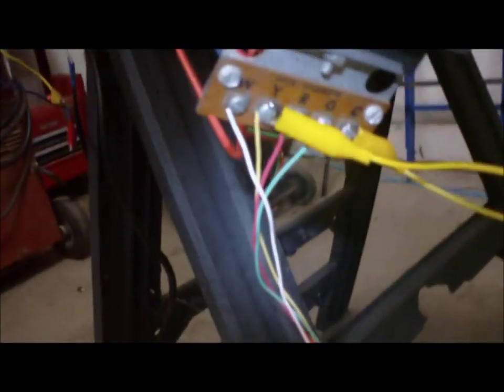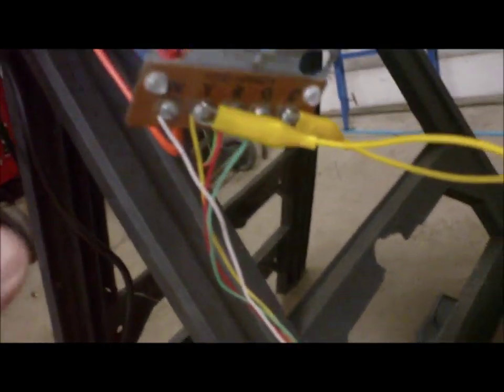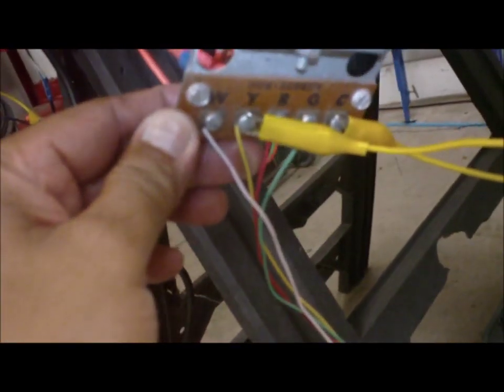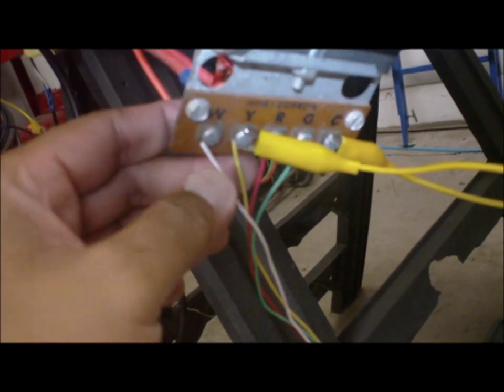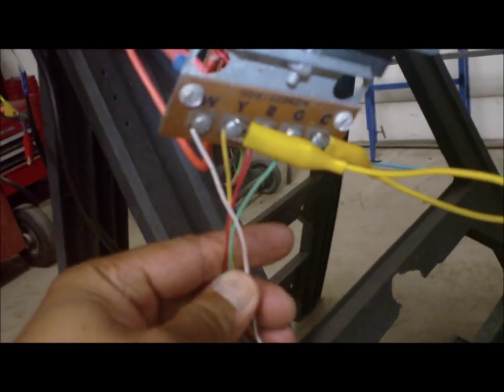It's 91 degrees in my garage. Right here is your low voltage terminal board, where you hook up all your thermostat wires. And right behind here, as you can see, is your transformer. This is your secondary, and right behind here, I don't know if you guys can see it, this is your primary, where your 120 goes in, common, and your voltage.